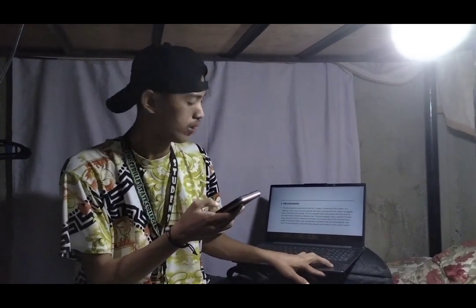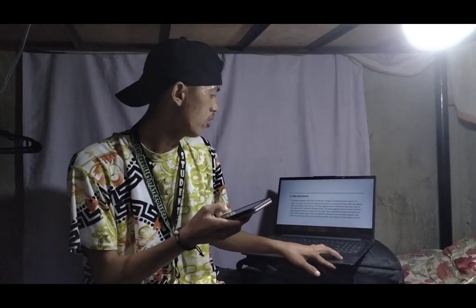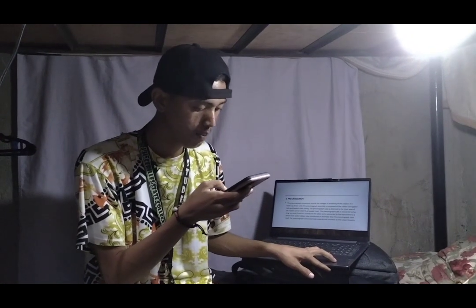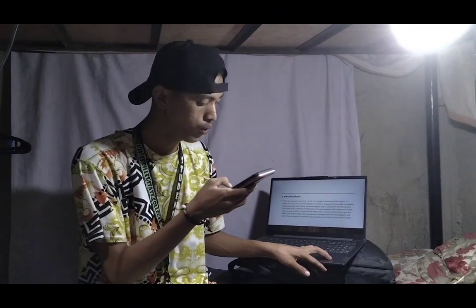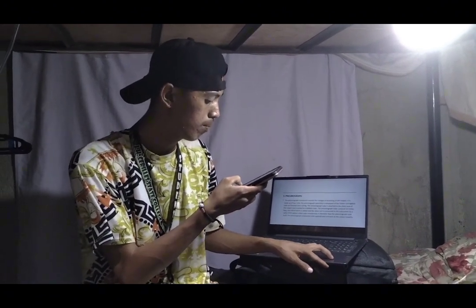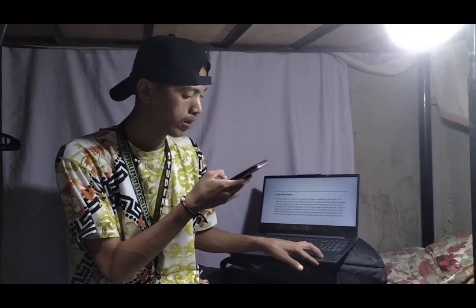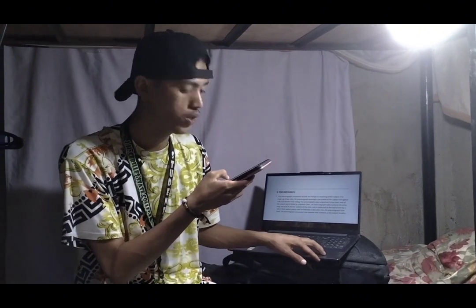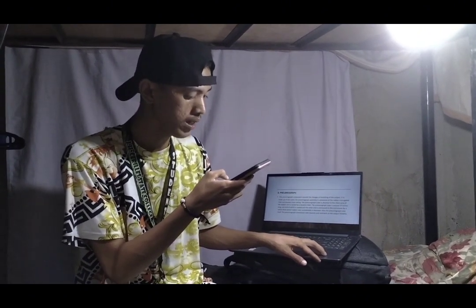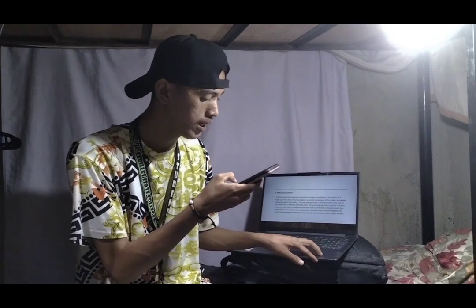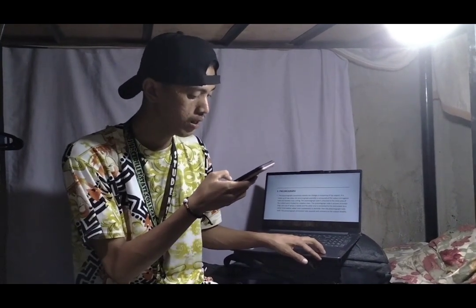Number 3 is the pneumograph. The pneumograph records the changes in breathing of the subject. It is made up of two units. The pneumograph assembly is composed of the rubber corrugated tube and beaded chain tubing. The pneumograph is attached to the chest area of the subject and is locked by a bead chain. The pneumograph is around 10 inches long.